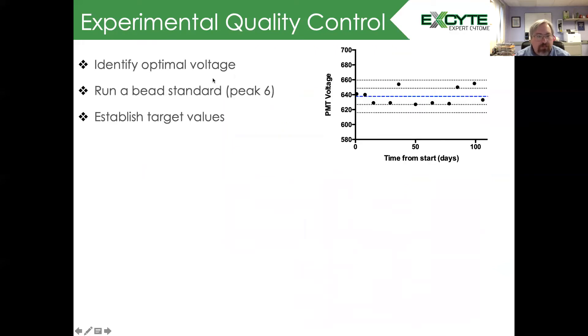It's important not just to do instrument quality control, but to think about experimental quality control. For example, we can use a peak six bead or any bead that you like that's fluorescent in multiple channels. After you've identified the optimal voltage, every day you sit down to run your experiment, you run that bead standard with the target values.